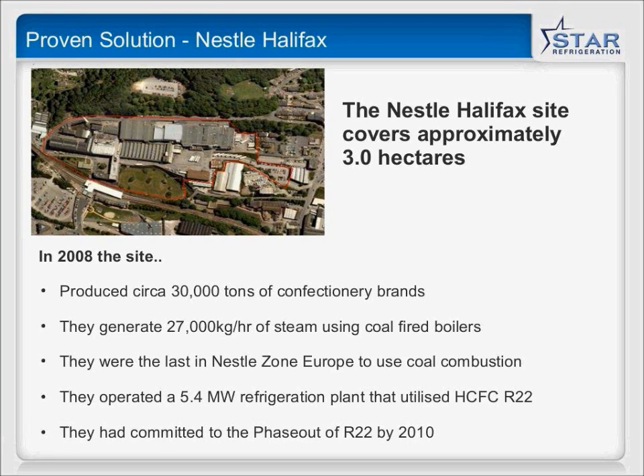What actually happened was that the chillers they had on site, which were making a noise, the fans were spinning, and they were delivering cooling to the process, so in a certain assessment they were working. In reality, they were so limited in their design and limited in their maintenance that there was an opportunity to replace them with something that was a design change for the better. So they went from an HFC or HCFC, in this case R22, which is being phased out pretty soon.